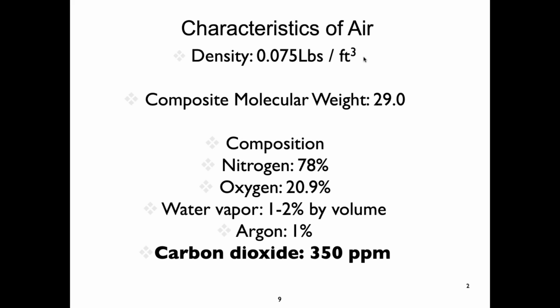What is it now? Anyone hazard a guess? Probably about 410 parts per million now, worldwide average, right? And you would literally measure that if you stuck this instrument out the window: 400 parts per million. If you're down on the street, it might be higher because you've got traffic, cars producing a little extra CO2, especially on 125th Street, where there's a lot of traffic, right? That is the stuff of global warming, CO2 being put into the air and accumulating in the air. So there are important changes in the ambient outside air.